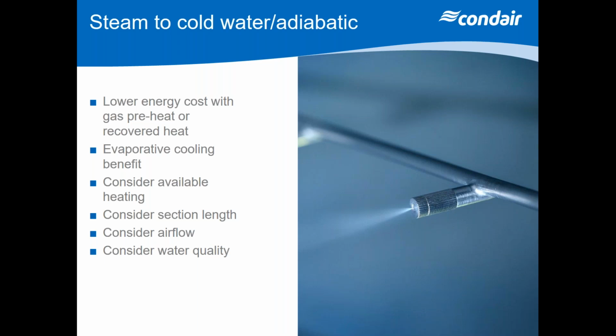Also, you're going to have to consider section length now with these units, because if you go for a spray system, if you look at high pressure spray, you're going to need a longer distance length to get that cold water system into place and get it to evaporate correctly.